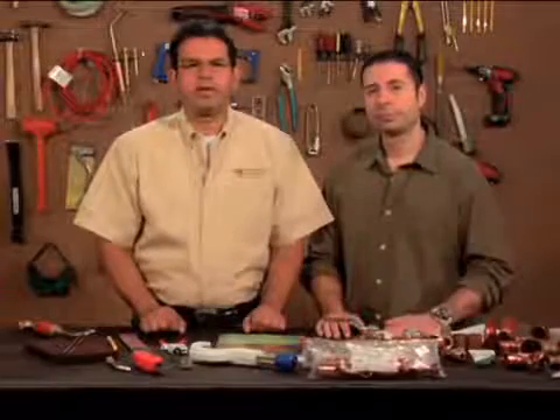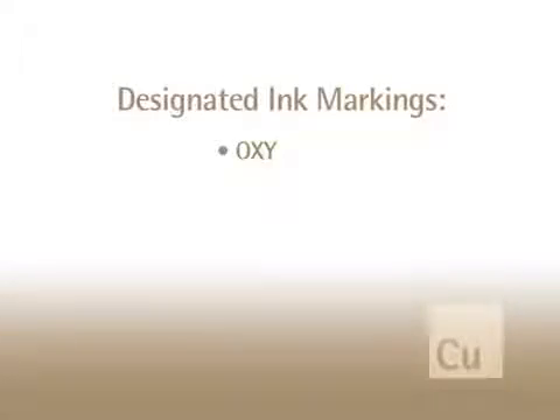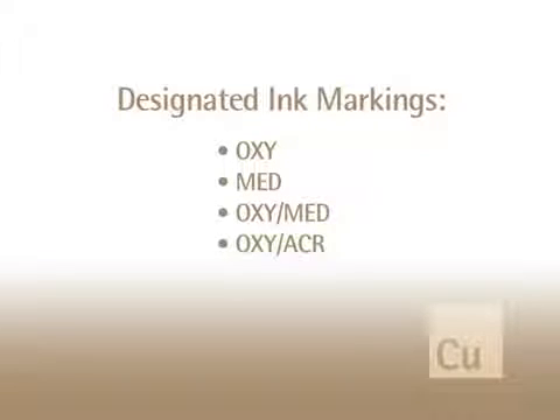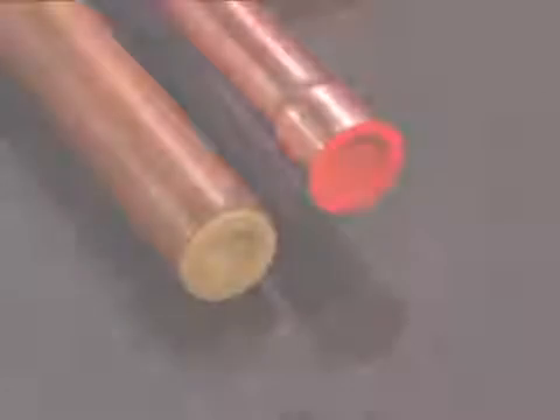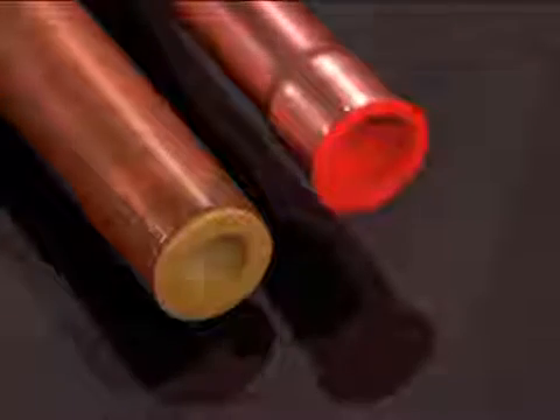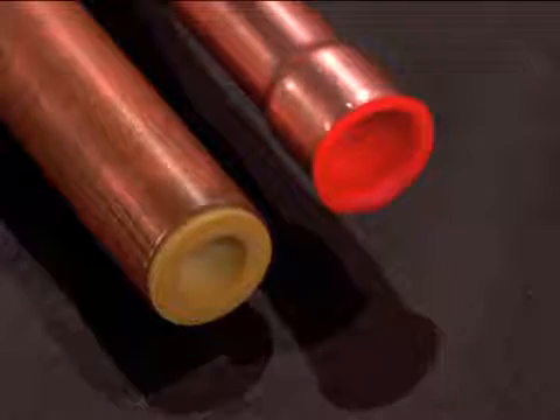These will include an ink marking in any of the following 5 ways: OXY, MED, OXY/MED, OXY/ACR, or ACR/MED, signifying that it is for medical gas use. The tube is cleaned and capped at the factory to protect it from any contamination.